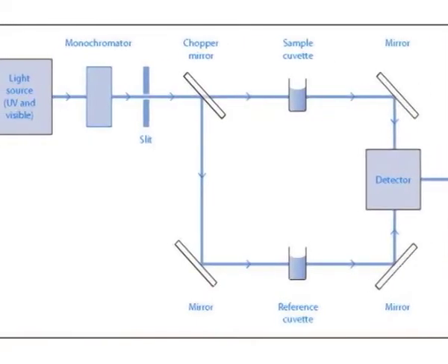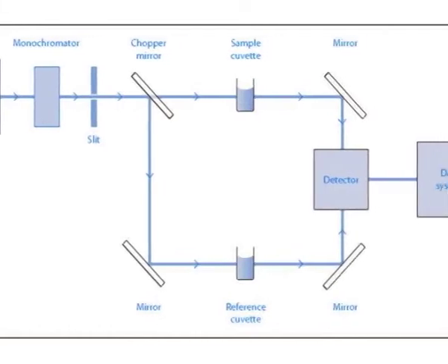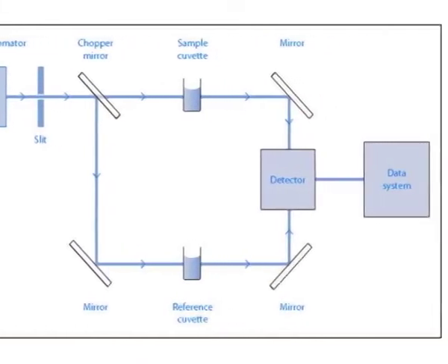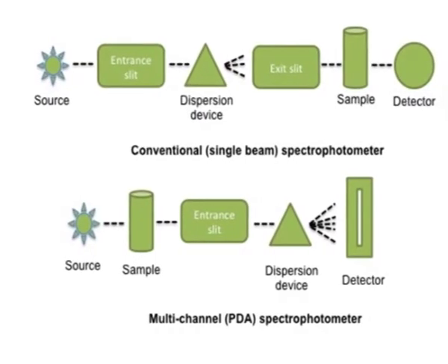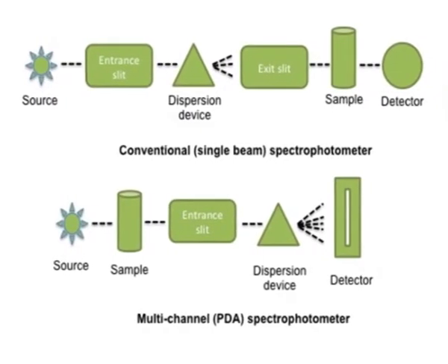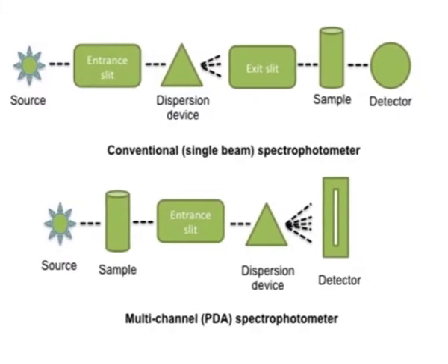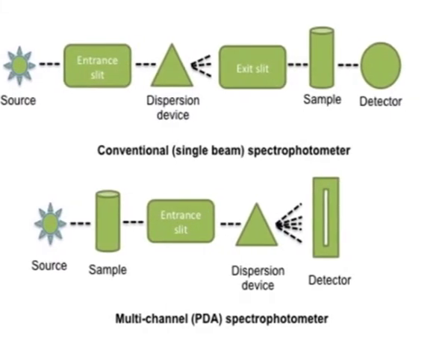Instability factors due to lamp drift, stray light, voltage fluctuations do not affect the measurement in real time. Little or no lamp warm-up time is required. This not only improves throughput of results but also conserves lamp life. We have seen that the double beam system design features far outweigh the advantages offered by single beam systems.